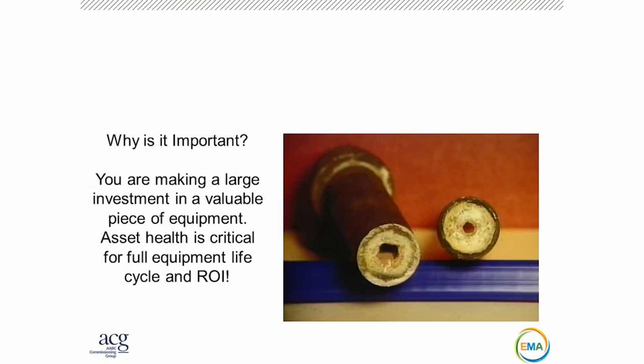So water treatment in general, why is it important? Okay, everybody in this room protects some sort of an asset. Those assets cost a lot of money. Even small boilers, maybe it's $50,000, could be more, could be less. You want to protect those as long as you can. The average lifespan of some of this equipment could be 30 years. It could be 6 months if it fails. And ultimately, when it does fail, they're going to come looking for you or me and ask why. So really, that's the goal here: increase that life cycle of the equipment, get your money out of that piece of equipment, and don't change it constantly because you didn't take care of it.